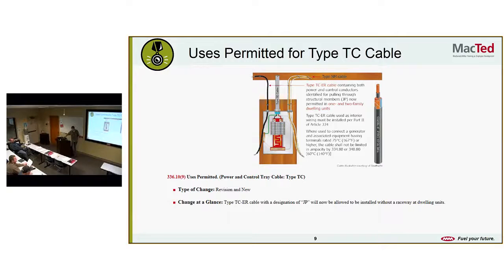Use is permitted for type TC cable. Type of change is a revision, and it's new. Type TC-ER cable with designation JP will now be allowed to be installed without a raceway in dwelling units.